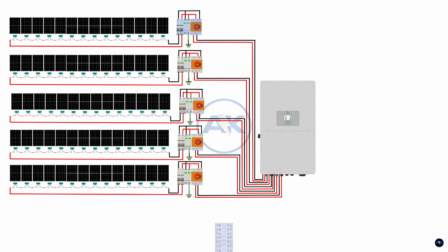Step 5. Battery to inverter connection. Now we'll connect the high-voltage lithium battery system to the inverter. This step is critical, so take your time and follow the sequence exactly. This system uses a 60 kilowatt-hour high-voltage lithium battery with a nominal voltage range from 160 volts up to 800 volts. Because this is high voltage, incorrect connections can be extremely dangerous.